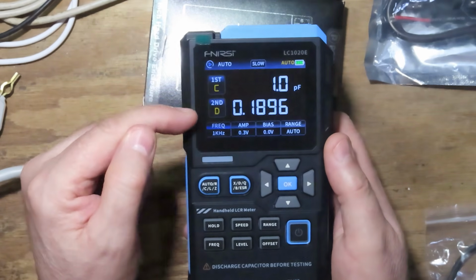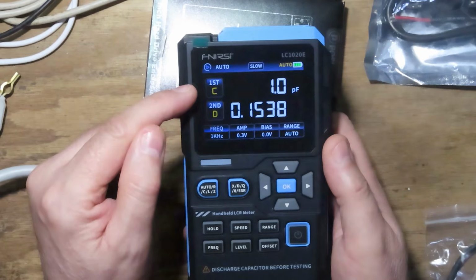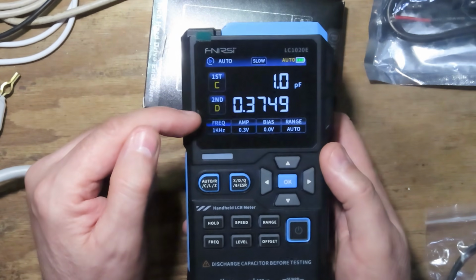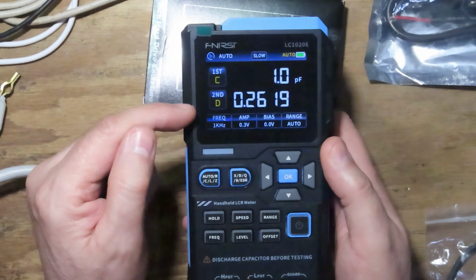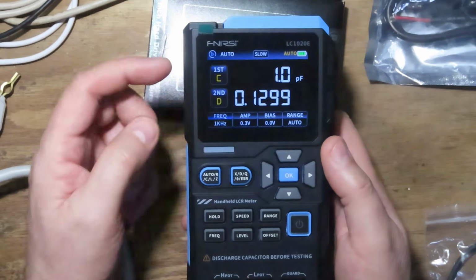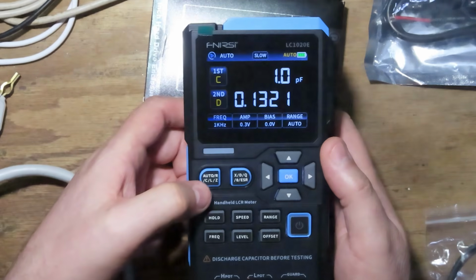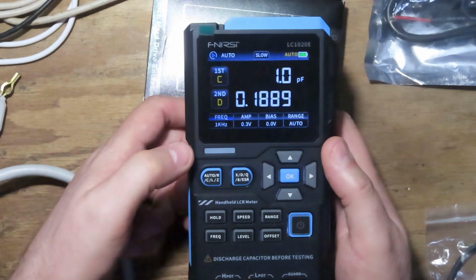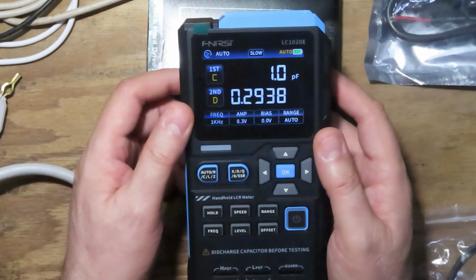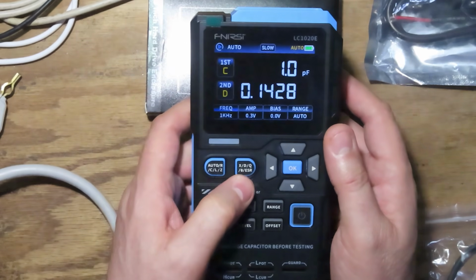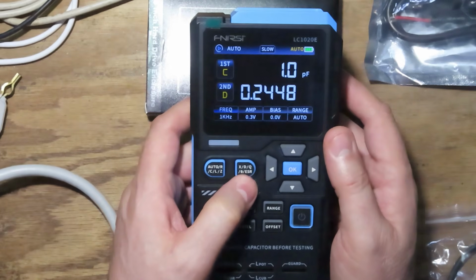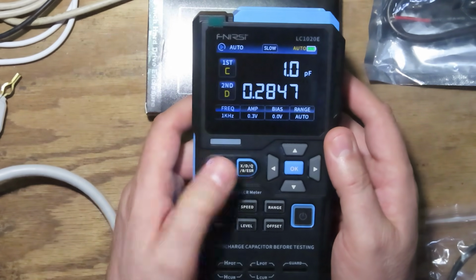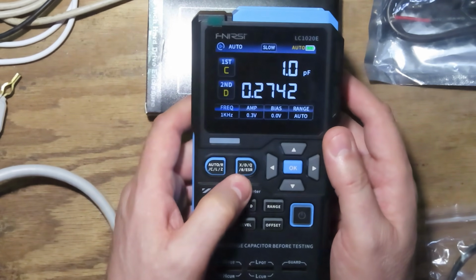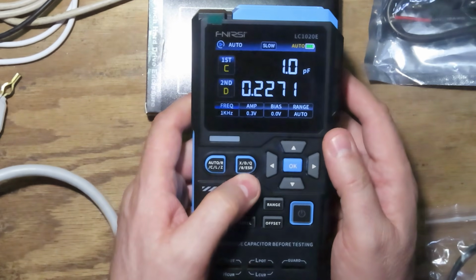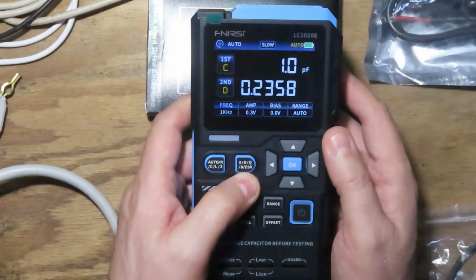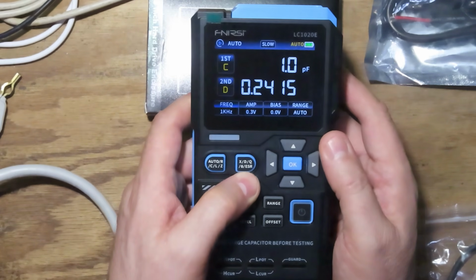We have 2 measurements. The first one is now set to capacitance, and the second one is set to D for dissipation factor. Our options are, for the first one, capacitance, inductance, impedance, and resistance. On the secondary, we have X, which is reactance, D for dissipation factor, Q for quality factor, phase angle, and ESR, equivalent series resistance, for testing capacitors and determining their quality or age.